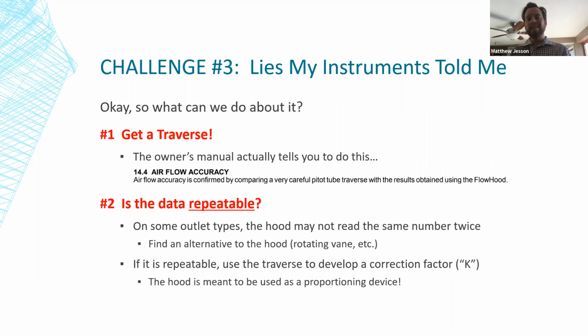If you do get a consistent result, even if it isn't an accurate result, like if you are reading an outlet and the hood tells you it's 150, but your duct traverse tells you it's 125, then you can just develop a correction factor, a K factor. And this is what the manual tells you to do. And the hood is meant to be a proportioning device, not so much an airflow measurement device, but a tool for proportioning the outlets.